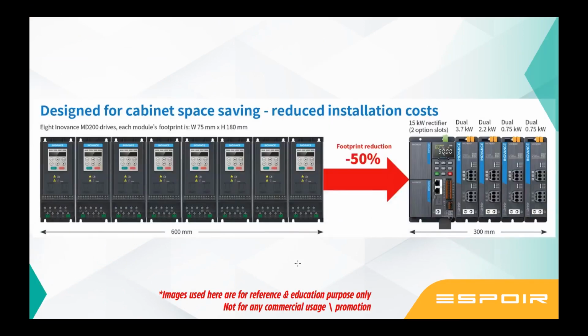Now, modular drive, there is one. You can see these are all independent drives, compact, still it is larger. Now the new designs have come. You can see you can connect 6 or 8 drives in a single power pack. The input is only one. You can see every module is an independent module like a PLC IO module. Only the output is there, UVW. You can just plug in the motor.